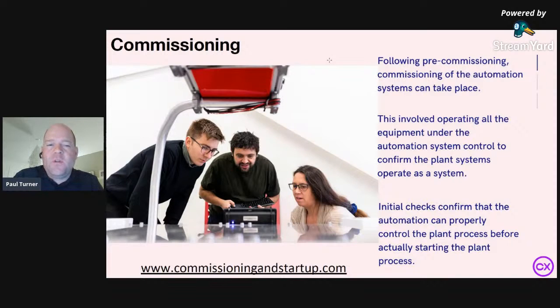This is the testing that would take place prior to starting the plant. This would be verification of the detailed or complex process logic functions in the field. This is really where some of the tests that were completed in the FAT are now completed in the field, to confirm that the logic functions with the end devices actually installed are functioning correctly per the PCN and the FRS.